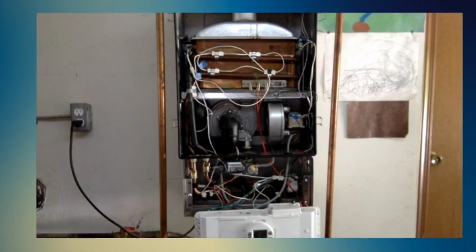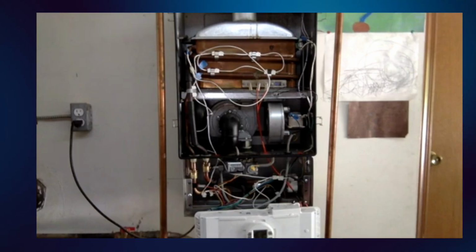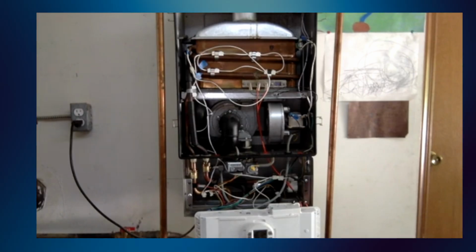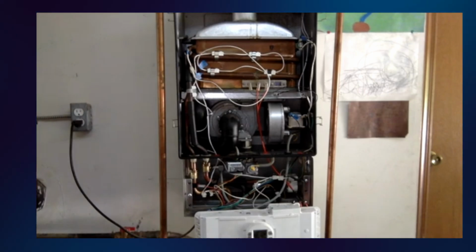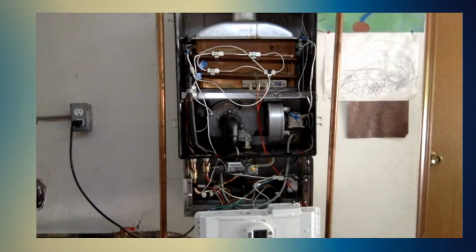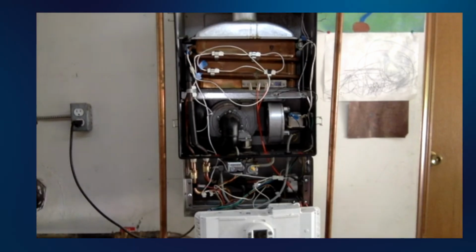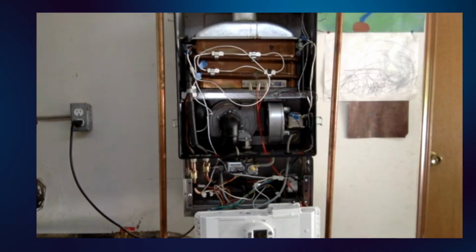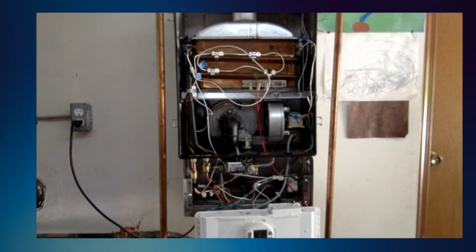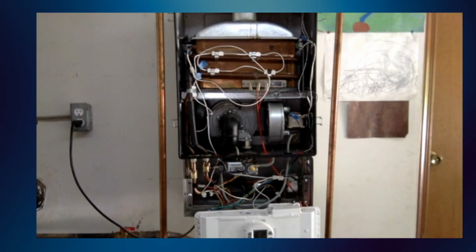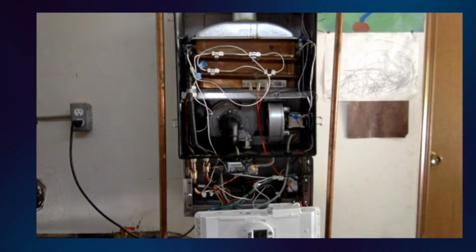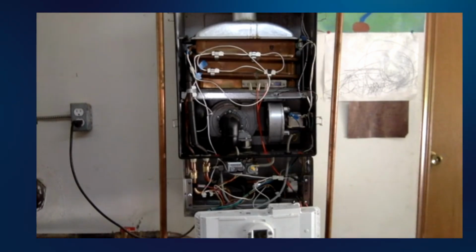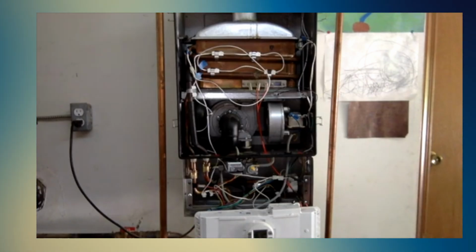The eighth cause is a flame sensing problem. Boilers need to detect the flame after ignition. This is often done through an ionization electrode or flame sensor. If the sensor is dirty, damaged, poorly positioned, or if the lead is loose, the flame may actually be present, but the control board may not recognize it. That is why a boiler can light briefly and then shut down. The flame exists, but the boiler cannot prove it safely.